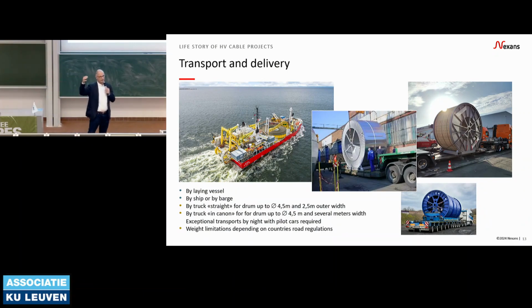This is the maximum gabarit we can use. And then we have to lose time, because even though the cable is produced during the day, you have to wait for night to transport your drums. And you do not need to transport just one drum, but 3 drums, because you have 3 phases. If you have 2 circuits, that's 6 phases. Imagine 6 trucks on the road at night with pilot cars at the front and the back, just to bring your cable on site.